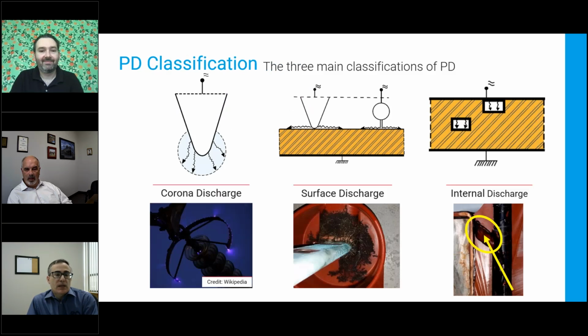There's a few different types of PD. There's corona discharge. This is like a sharp edge, like the threads of a bolt or a bracket that's in the electric field. Typically, you find it in an outdoor setting, and there's a lot of YouTube videos you can see, especially nighttime ones, where it's very visible. It's not so much of an issue for insulation, but it does create a lot of noise. And in an enclosure, there's some gases that are created if you have this occur in an enclosed cabinet where there's no air circulation. There's a reaction. It starts with ozone and ends with nitric acid that can create rust.